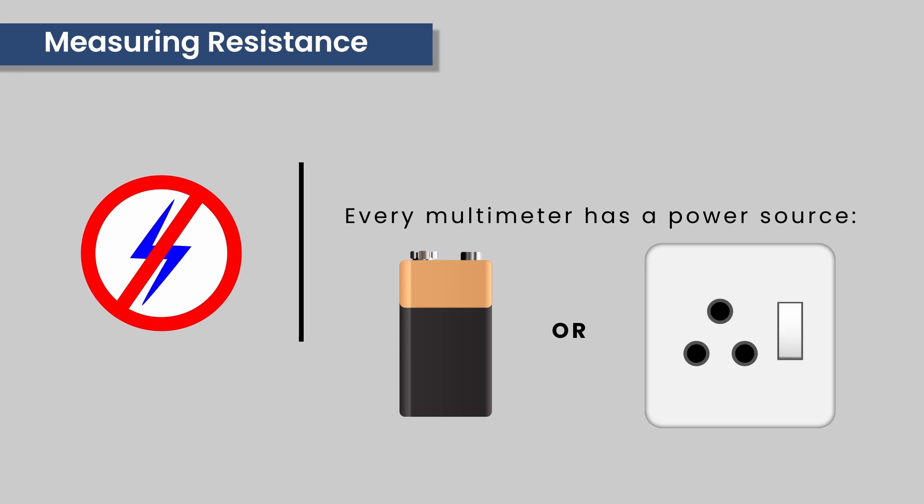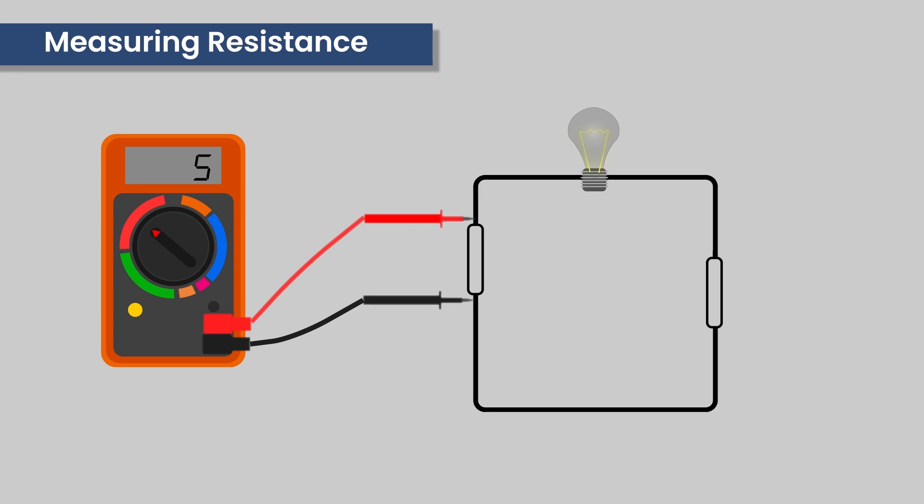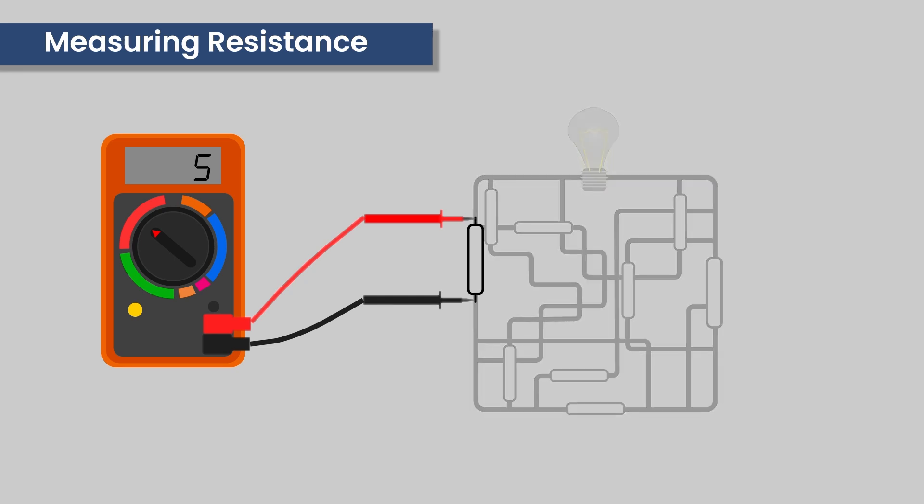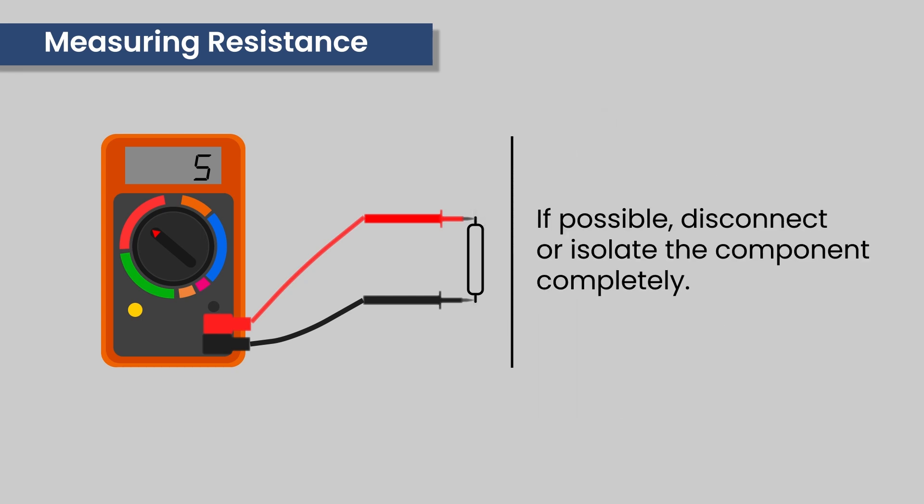Voltage is induced into the circuit or device by the multimeter and the resistance is then measured and displayed. When more complex circuits are measured, make sure that you are only measuring the resistance on one component or the reading will not be accurate. If possible, disconnect or isolate the component being measured.